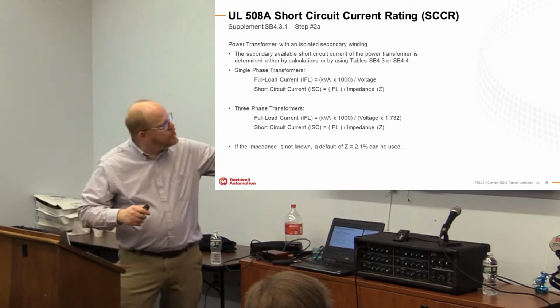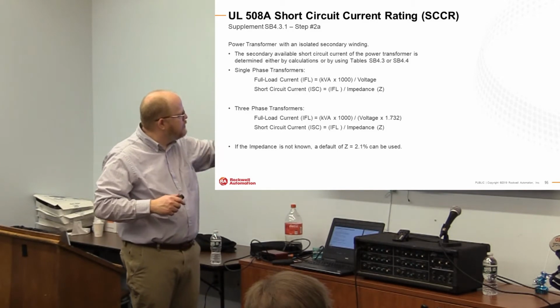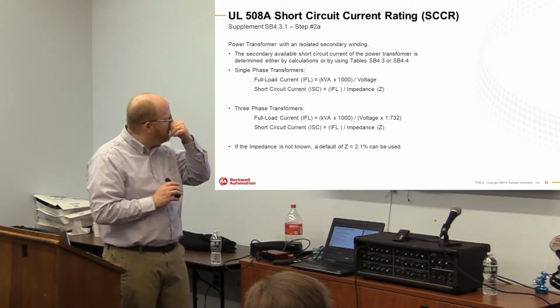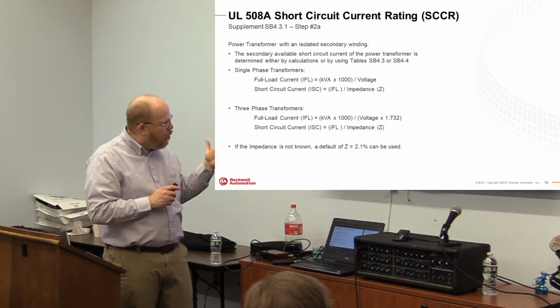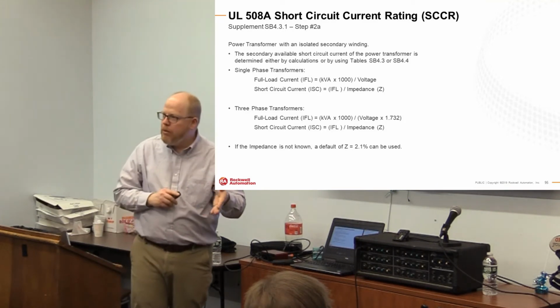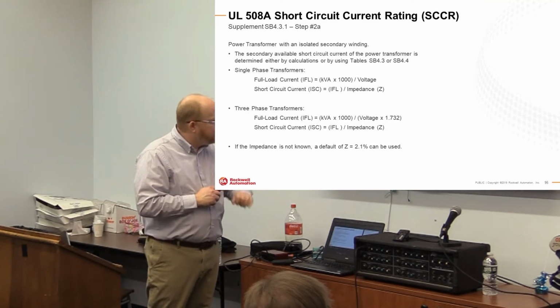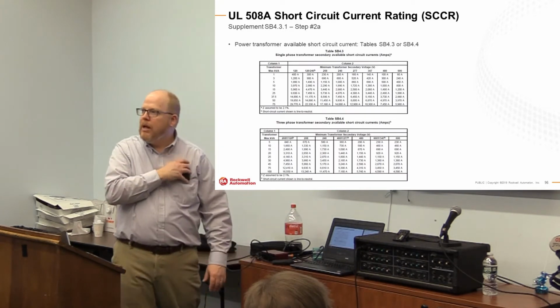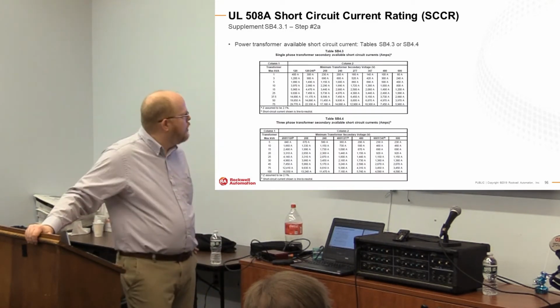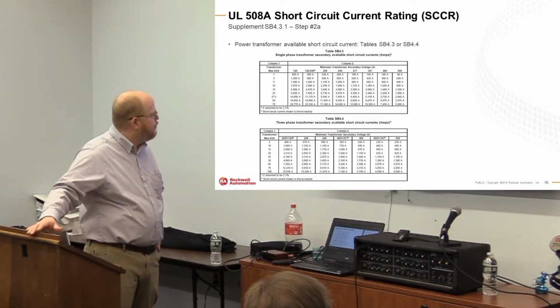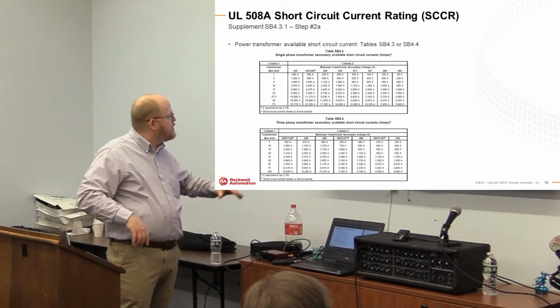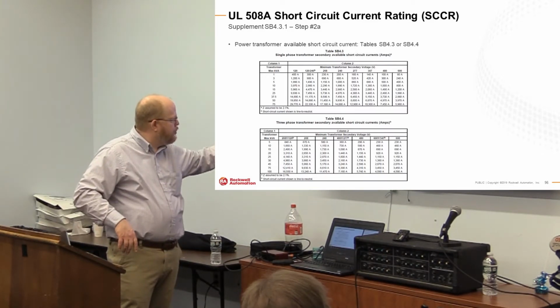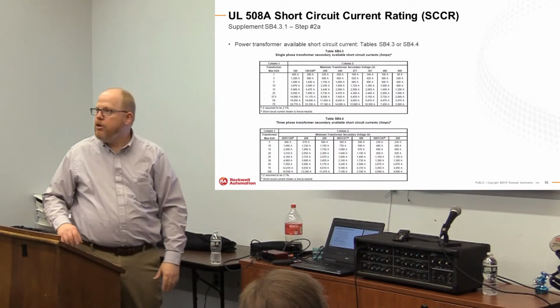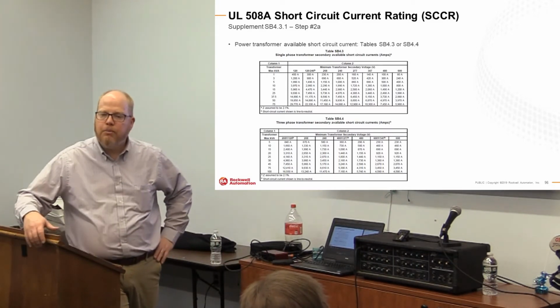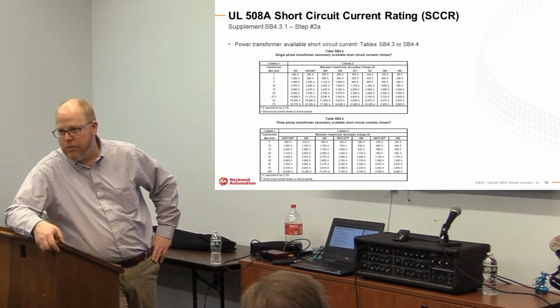There are some calculations you can do here, right? There are some formulas that you can determine, or if you would choose to just use a lookup table, you assume an impedance of 2.1% transformer, and these tables then become your source of data. And you can see here in an example of a single phase versus a 3-phase transformer, and you're able to look at the available let-through current of that transformer.